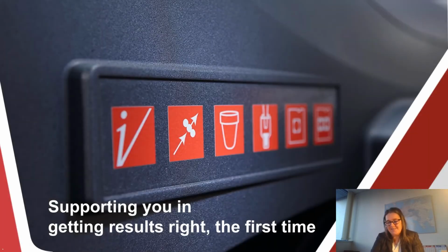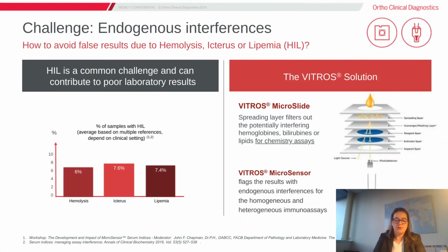Definitely, analytical errors are a reason to worry, but let me give you some reasons now not to worry and give you specifics on how we overcome these challenges. Well, microslides bring a solution to interferences thanks to its technology. The challenge of hemolysis, icterus and lipemia can occur on average in about 7% of samples. In the emergency department, this could even go up to 30% of hemolyzed samples. So this is a quite common and an impacting issue.